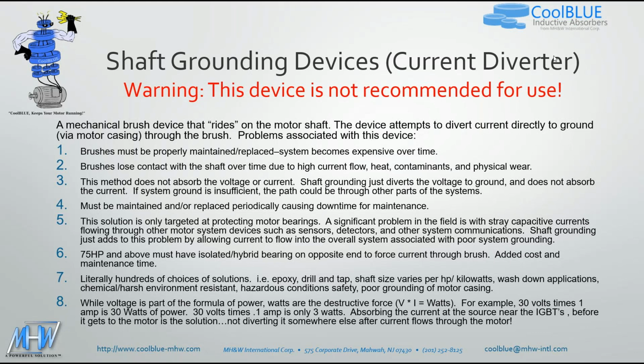If the system ground is insufficient, then the path could be through other parts of the systems. I believe that makes sense, that if you don't have a good ground, then the voltages and the currents will find an alternate path, and this is what creates problems in other systems. It must be maintained and replaced periodically, causing downtime for maintenance. This solution is only targeted at protecting motor bearings. A significant problem in the field is with stray capacitive currents flowing to other motor system devices such as sensors, detectors, and any other type of system communications. Shaft grounding just adds to this problem by allowing current to flow into the overall systems associated with poor grounding.